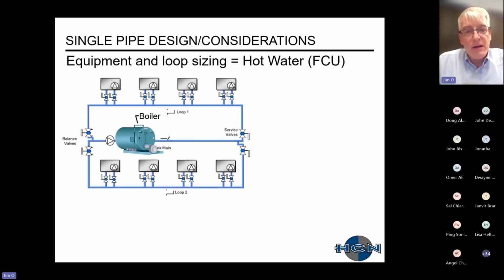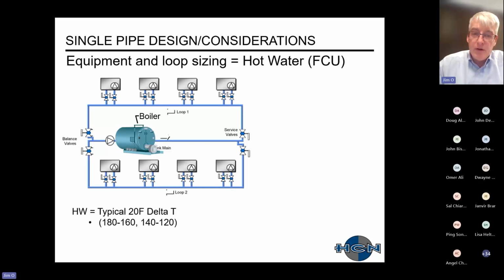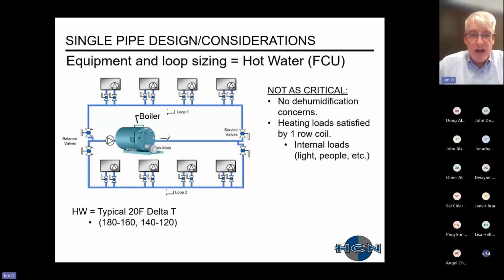Lastly, let's talk about single pipe systems for hot water. Your hot water typically has a higher delta T of 20 degrees. I've seen them up at 30 and 40 degrees, just because you don't have any dehumidification requirements. Also, my experience has been that you don't get calls for lack of heating, because you're designing for 0 degrees out here in Philly, which occurs every 3 years. And also there are a lot of internal loads with people and lights and such. And traditionally, if you look at fan coils, the heating load is easily satisfied with a 1-row coil.